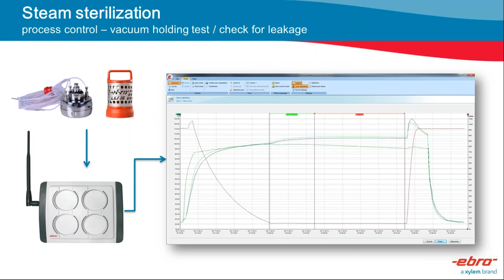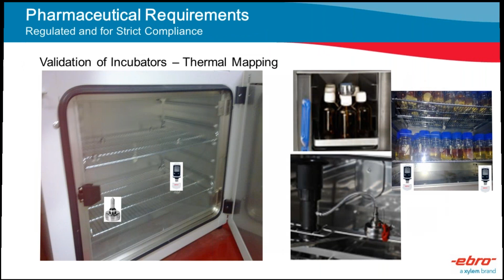And it's using the same software, the WinLog validation and the WinLog Med. That's how it looks like. And it will give you an indication whether it's passing or failing. And these are the different other applications in the pharma. We can have the validation also for incubators and for refrigerators. We have the new logger specially made for validating or mapping refrigerators in your laboratories.